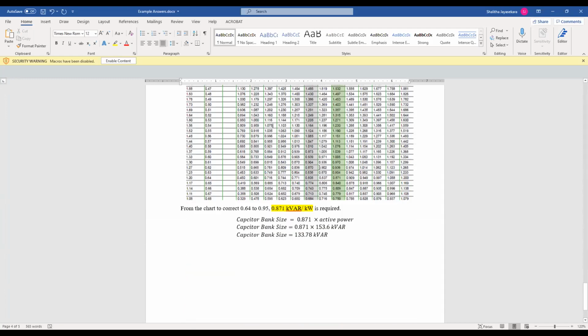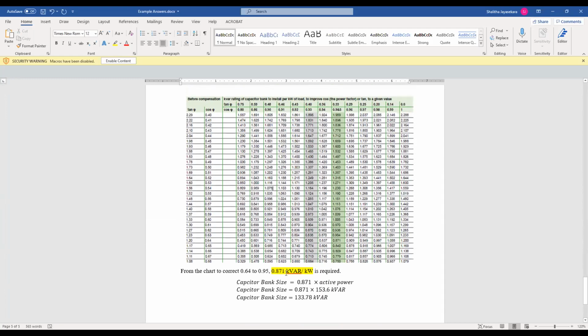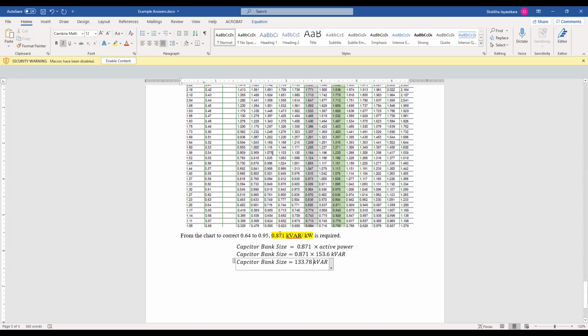Now from the simplified chart method, you have found the required compensation per kilowatt, or per active power unit. So we are going to size our capacitor bank, or the compensation amount, by multiplying this value by the active power in the system. Our active power amount is 153.6, our required compensation per kilowatt is 0.871, and your capacitor bank size will be 133.78.